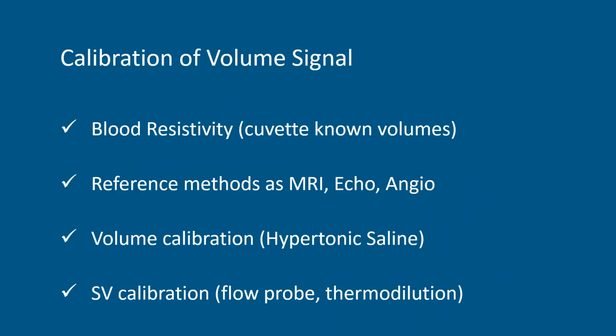Now, in terms of calibrating the volume signal, there are essentially four methods that have been used, even historically. One has been a relative common factor, used as early as the 80s, where they applied an in vitro calibration. They just put the conductance catheter in a plastic cylinder of known volumes, matched the resistivity with saline to that of blood, or even used blood itself, and constructed a calibration curve based on different volumes of cylinders.